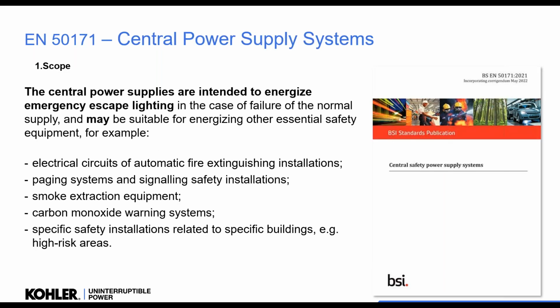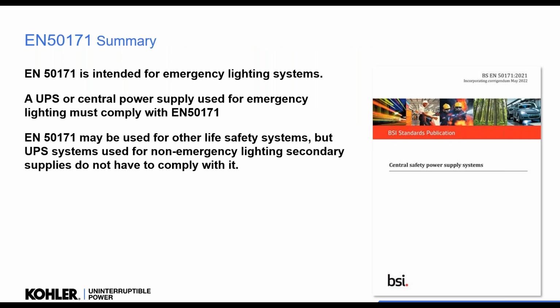All right. So 50171. Now this often causes some confusion because this is a central power supply system, and it is intended for energizing emergency escape lighting in the case of a failure of the normal supply, and it says it may be suitable for energizing other essential safety equipment, as with all the other equipment we've seen. Okay, it doesn't say you have to use it. So it is intended for emergency lighting.